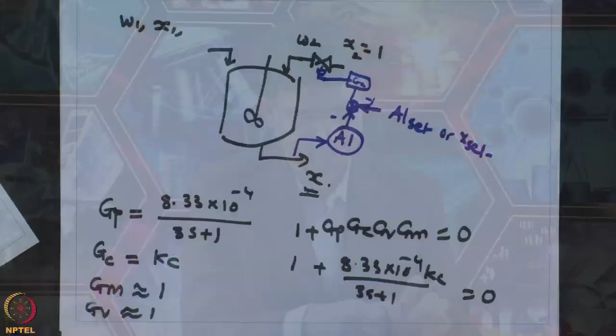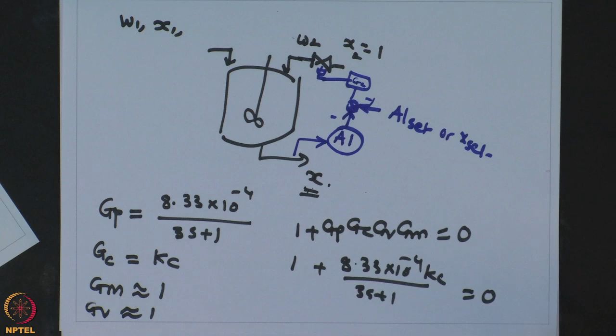What we are doing here is that we are measuring the composition, and accordingly the feedback system is taking an action. Now composition measurement is very slow. So typically temperature, pressure, level, or even flow, all these things can be measured almost instantaneously, and there is almost no lag between the change in the variable and what you get as the measured value. However, the same cannot be said about composition. Composition measurements are very tricky, and even though we have sophisticated instruments like GC, it will still have some amount of lag by the time you have the measurement in a digital form.